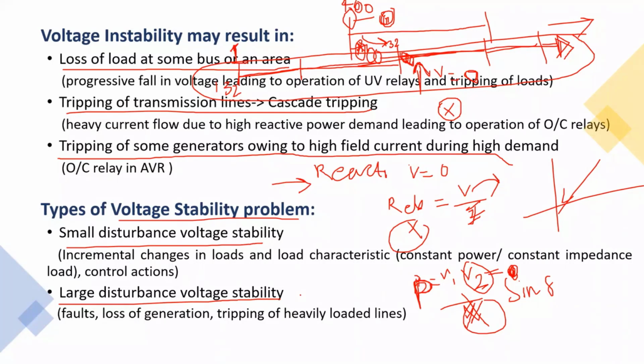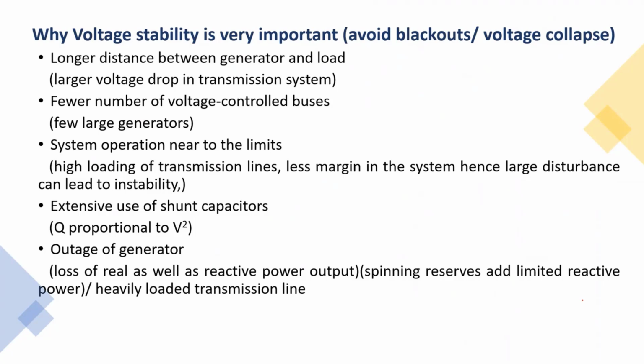So you are facing frequency problem, voltage problem and angular stability problem at the same time. Which one will trigger first? It depends upon which one is nearer to its stability limit: the frequency stability limit, the voltage stability limit, or the angular stability limit. So either of them can hit first. But certainly after the first limit is hit or any tripping happens, other instabilities follow, cascading occurs, and everything comes together, resulting in a very significant disturbance in the system. That's why it is very important to avoid voltage instability problems, because it will help us avoid blackout and voltage collapse.